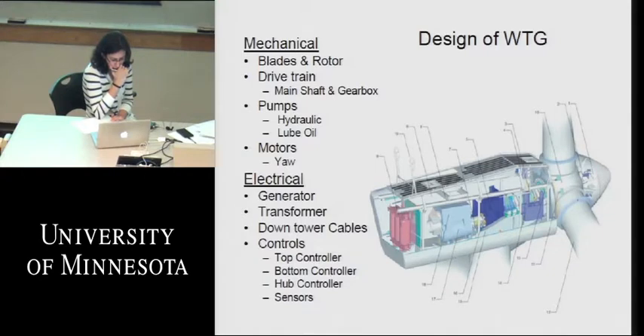If we make that transformation right outside the generator, then we save some energy losses going down the tower, and we can step up the voltage, which means conversely we can step down the current. In stepping down the current, we can reduce those I squared R losses because we drop the current significantly, in amperage from about 1,500 amps to about 40 amps. Your losses are the square of the current times the resistance in that cable, so if you can reduce the current from 1,500 amps to 30 amps, you get a significant savings in the heat losses in the cable coming down the tower.